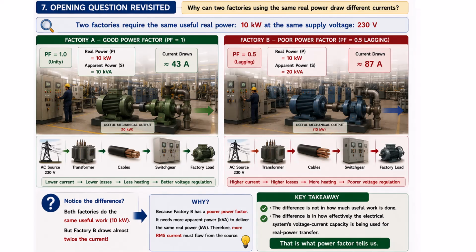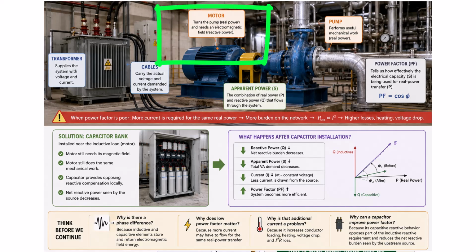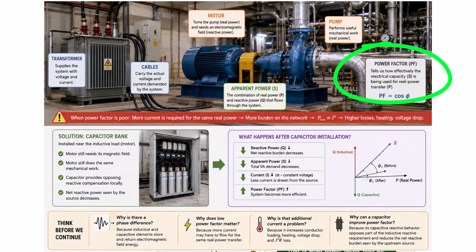Now return to our factory one final time. The motor turns the pump that requires real power. The motor also needs an electromagnetic field that introduces the reactive behavior. The transformer and cables must carry the actual voltage and current demanded by the system that give us apparent power. And power factor tells us how effectively that electrical capacity corresponds to real power transfer. When the power factor becomes poor, more current may be required for the same real power. More current means more burden on the electrical network, and because P loss is directly proportional to I square, that additional current matters enormously. Then engineers install an appropriately designed capacitor bank near the inductive load.